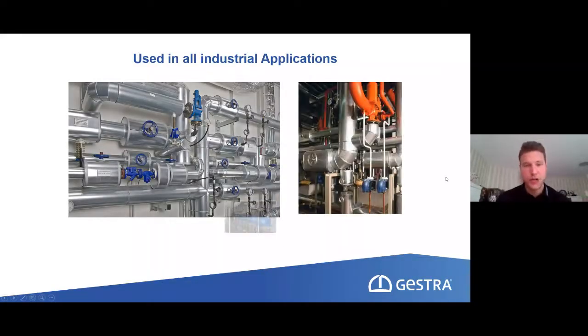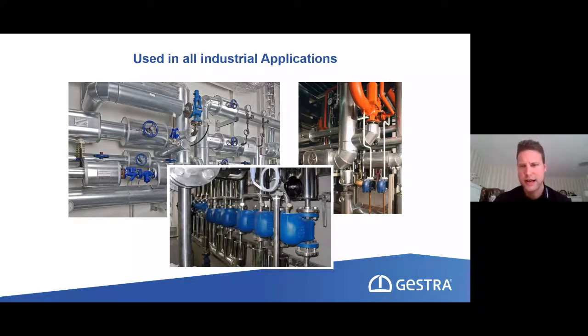All right. So steam traps are almost everywhere. As soon as we want to use a specific source of energy to heat up a product or to sterilize something, we will need a source of heat. And for us, it's steam. Steam can carry quite a high amount of heat. And we want to use that heat in a heat exchanger to transfer the so-called heat of evaporation to the product. And as soon as we did this in the heat exchanger, we will have a so-called phase transition. So the steam that I put inside the heat exchanger will start to condense and become liquid again.